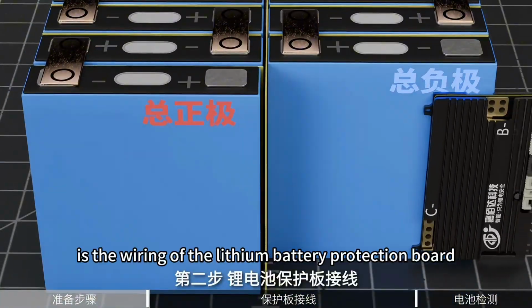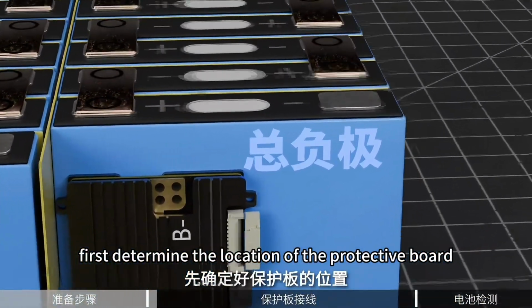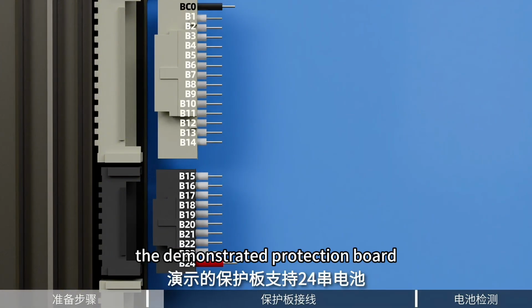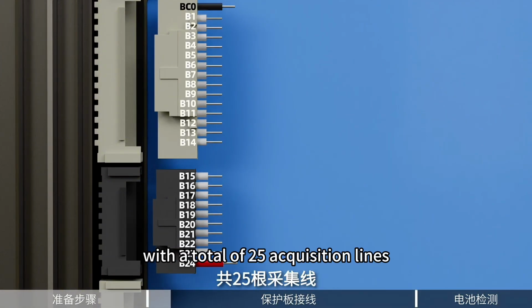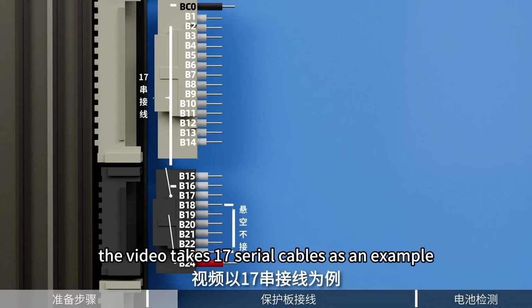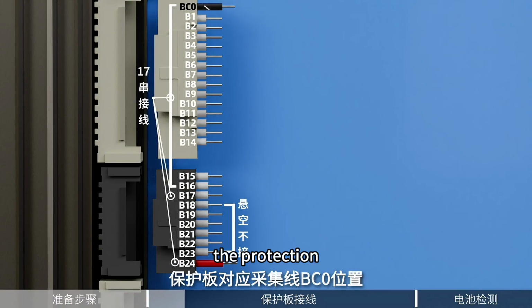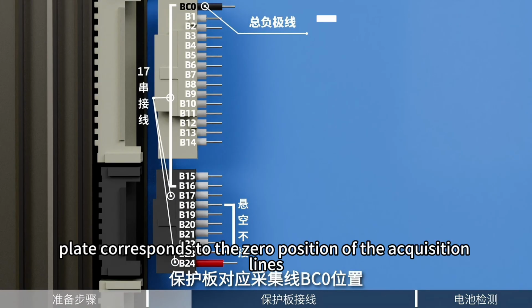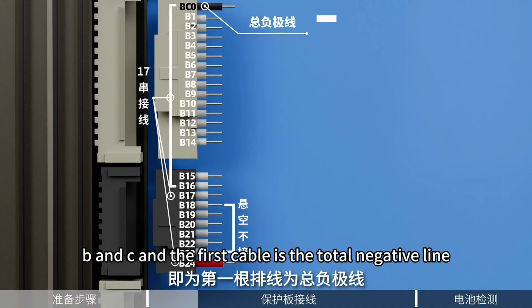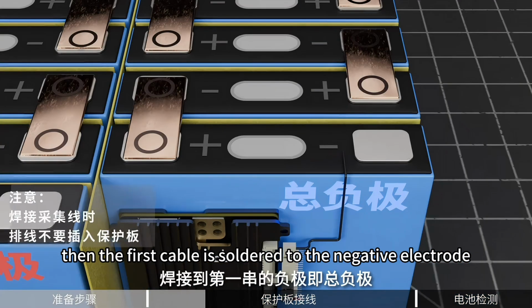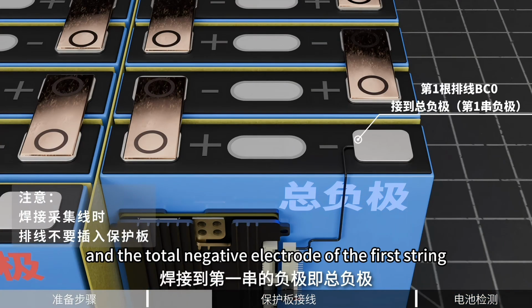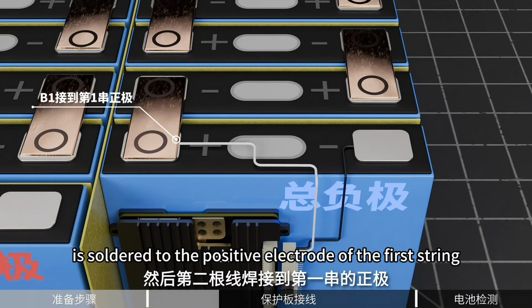The second step is the wiring of the lithium battery protection board. First, determine the location of the protective board. The demonstrated protection board supports 24 strings of batteries with a total of 25 acquisition lines. The video takes 17 series cables as an example. The protection board corresponds to the zero position of the acquisition lines, BC0, and the first cable is the total negative line. Then the first cable is soldered to the negative electrode and the total negative electrode of the first string. Then the second wire is soldered to the positive electrode of the first string.